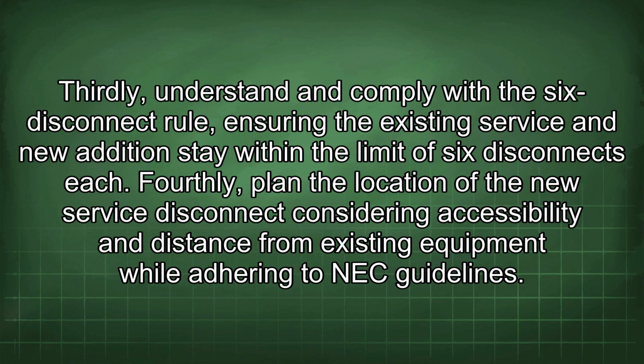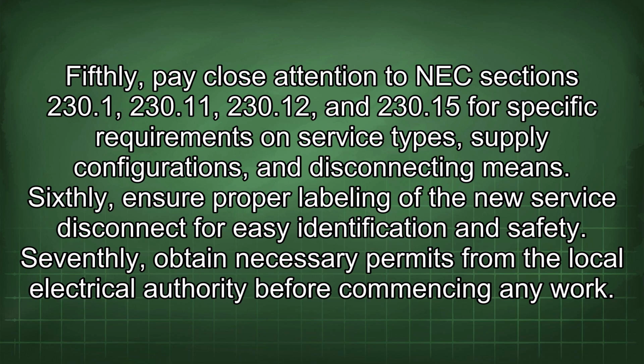Thirdly, understand and comply with the 6 disconnect rule, ensuring the existing service and new addition stay within the limit of 6 disconnects each. Fourthly, plan the location of the new service disconnect considering accessibility and distance from existing equipment while adhering to NEC guidelines. Fifthly, pay close attention to NEC sections 230.1, 230.11, 230.12, and 230.15 for specific requirements on service types, supply configurations, and disconnecting means. Sixthly, ensure proper labeling of the new service disconnect for easy identification and safety.